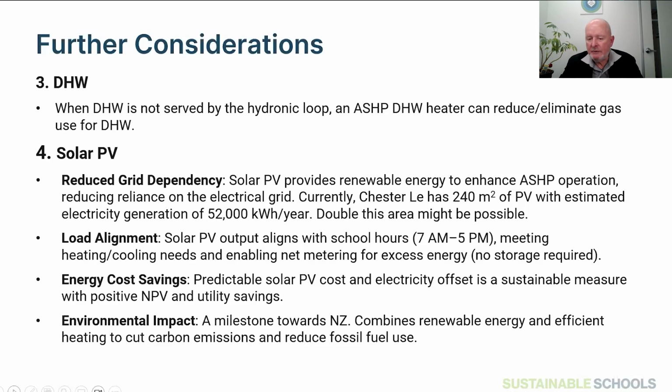There are air source heat pump domestic hot water heaters. We're not finding them for the volume used in schools. We're not finding them cost effective right now. And I don't believe that either Ottawa Catholic or Toronto District is using them at the moment.